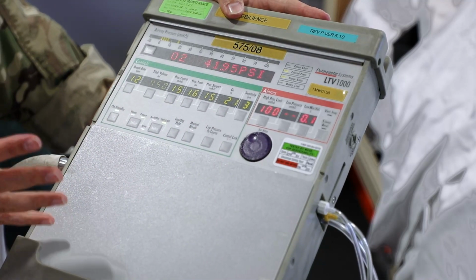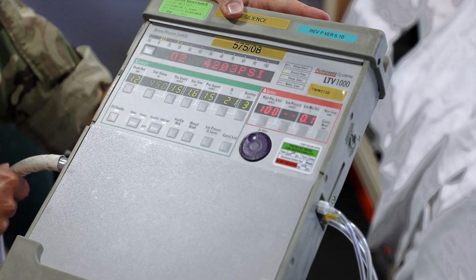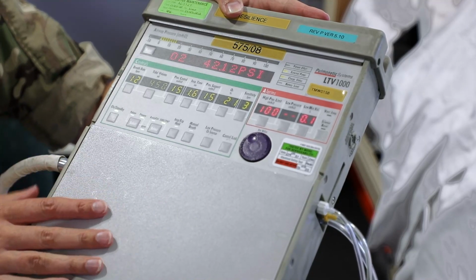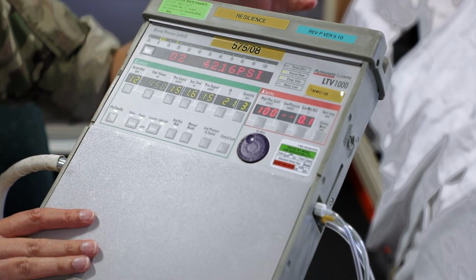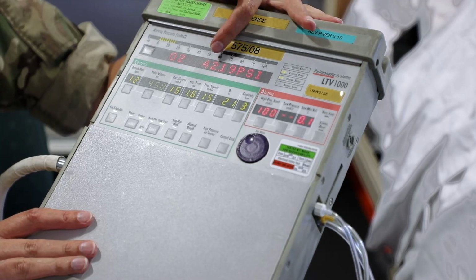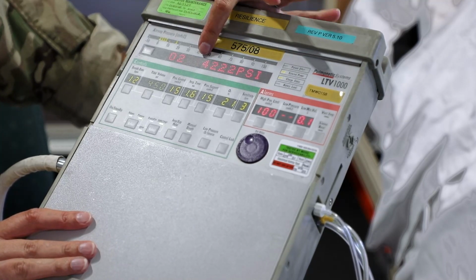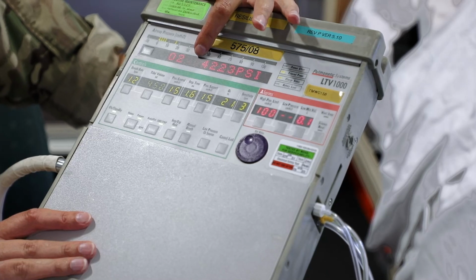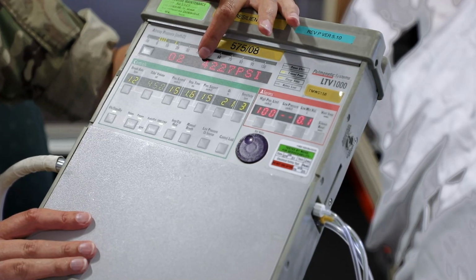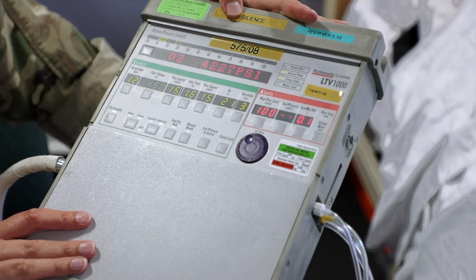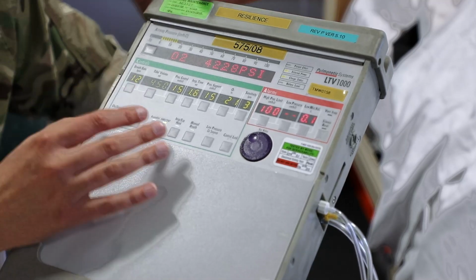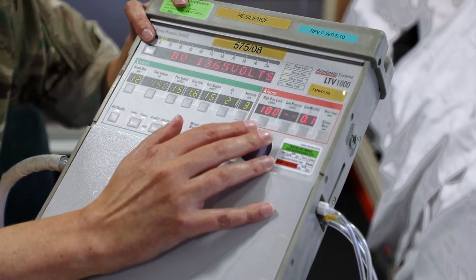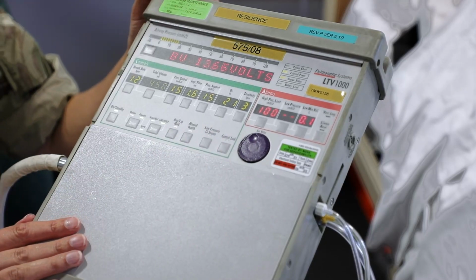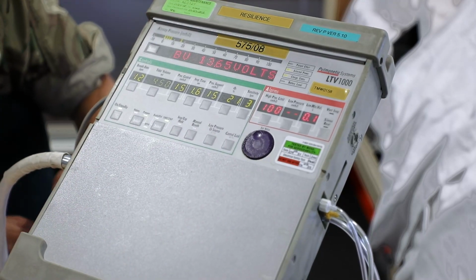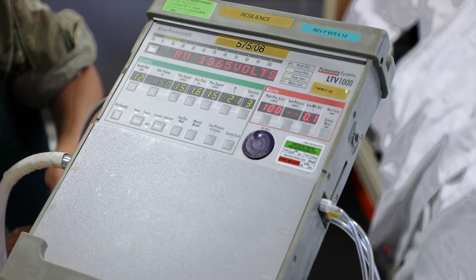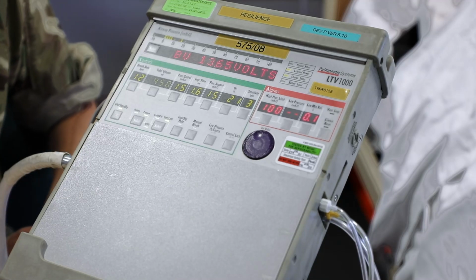In this instance, we're using training kit, so the hosing isn't always that effective, and we often use only partly full oxygen cylinders, hence why the PSIs are quite low. But what you're looking for here is a PSI of around 55, but greater than 40 is sufficient. Next, we're going to look at our battery voltage. Obviously this is connected to the mains at the moment, so when I disconnect, it's going to alarm me that the battery is disconnected.